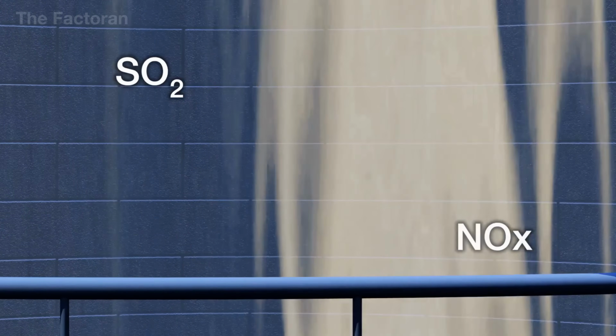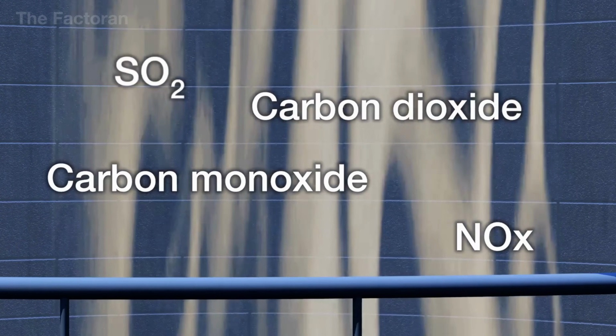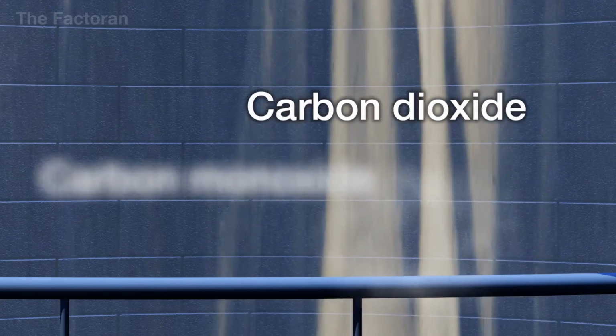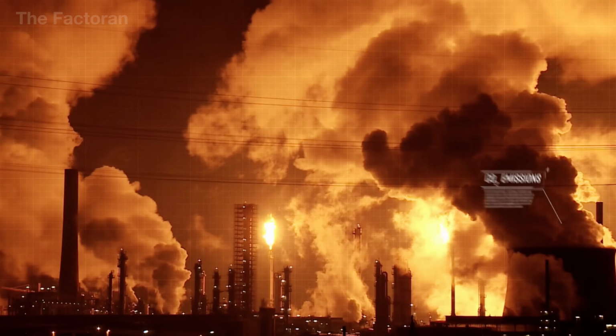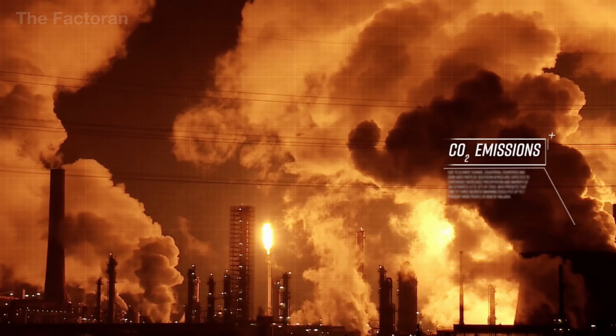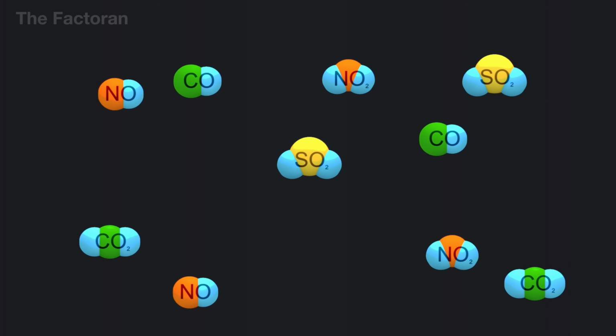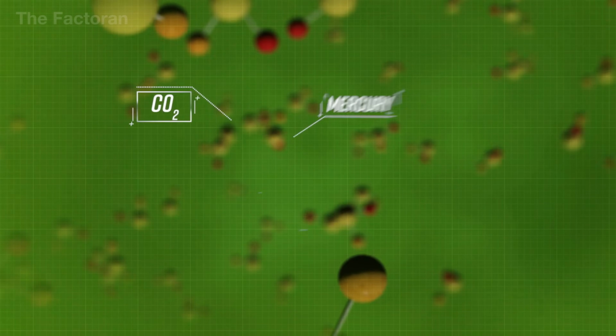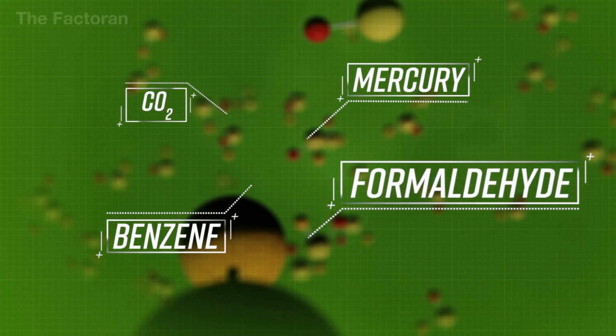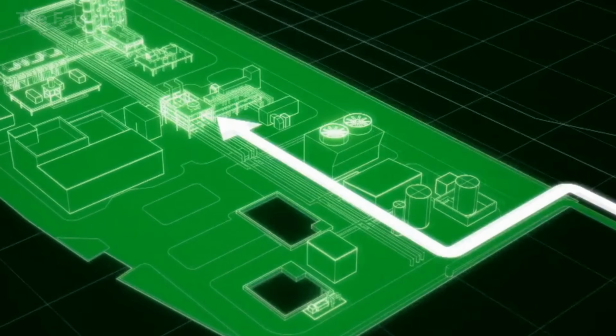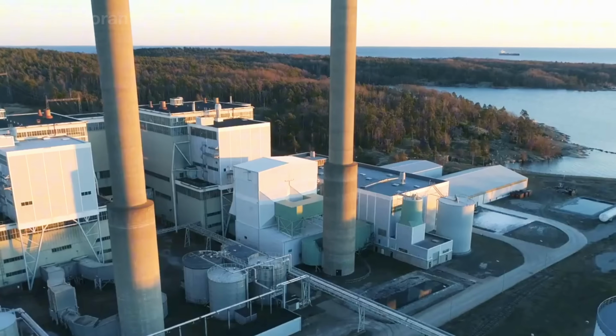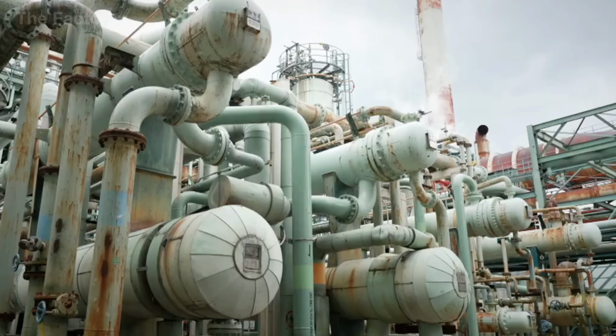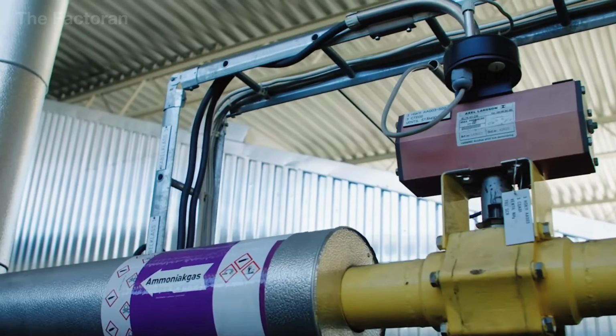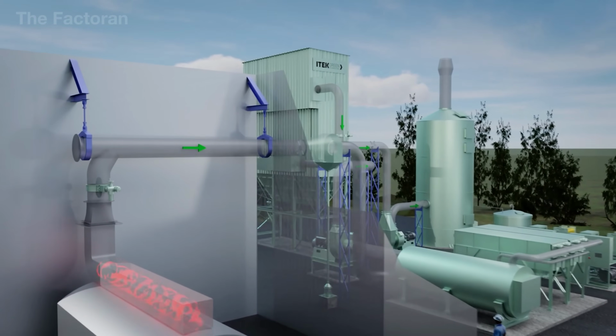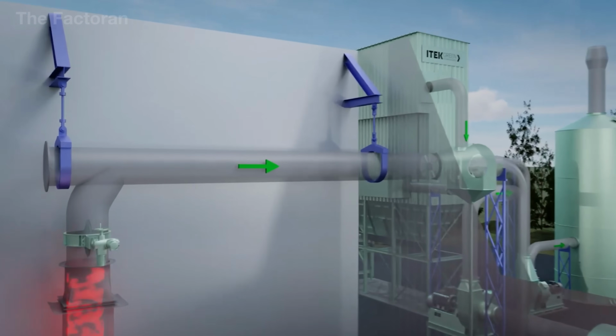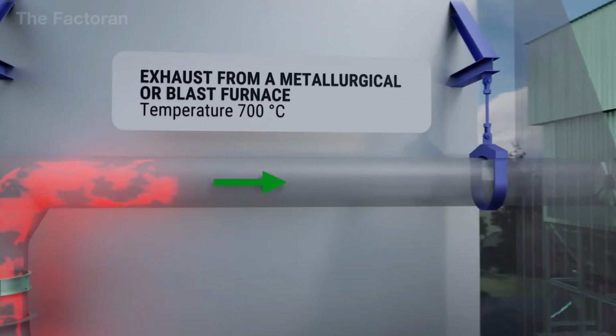The collected exhaust typically contains SO2 from sulfur in the fuel, NOx produced in high-temperature combustion zones, and CO and CO2, byproducts of the burning process. Depending on the production type, the gas may also contain acid vapors, fine dust, or heavy metal fumes. Once captured, the gases are conveyed through heat-resistant, corrosion-proof metal ducts, usually made of carbon steel coated with ceramic or 316L stainless steel, capable of continuous operation at up to 600 degrees Fahrenheit.